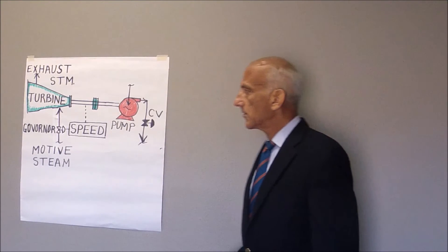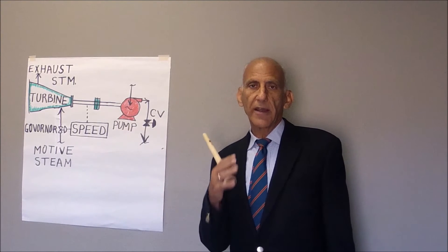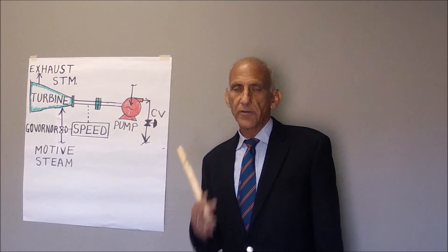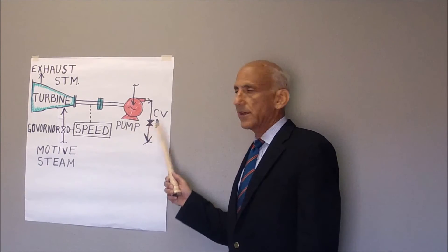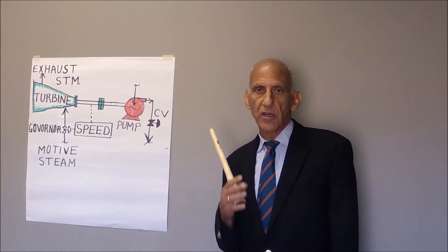In order to select the optimum turbine speed, what you need to do is look at the position of the control valve on the discharge of the pump.